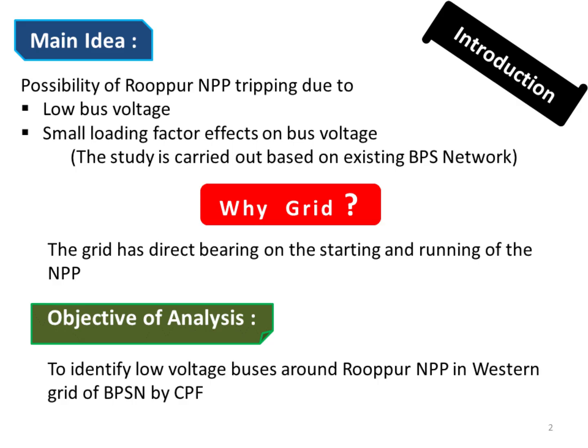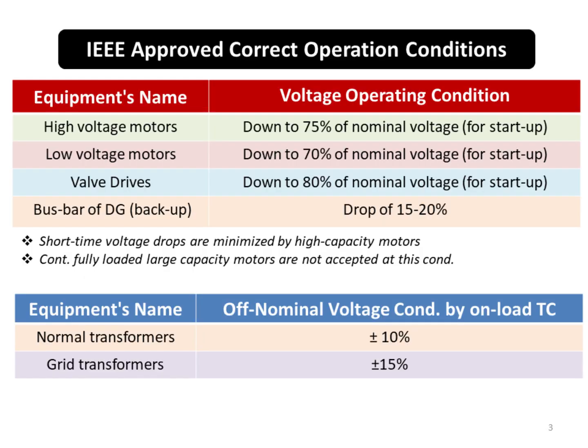The main concern is the risk of Rooppur nuclear power plant tripping due to low bus voltage, especially under small loading conditions. This study uses the existing Bangladesh Power System Network, called BPSN, as the basis for analysis. The grid directly affects the nuclear power plant, called NPP, startup and operation, so identifying vulnerable buses is critical. Our objective is to use continuation power flow, CPF, analysis to locate low-voltage buses in the western grid near Rooppur.